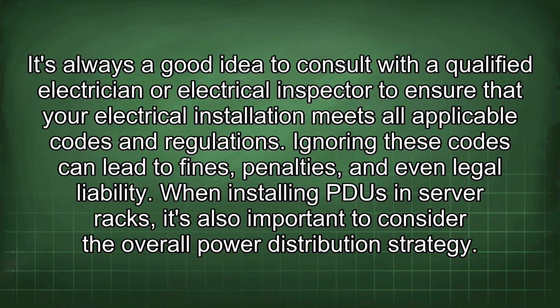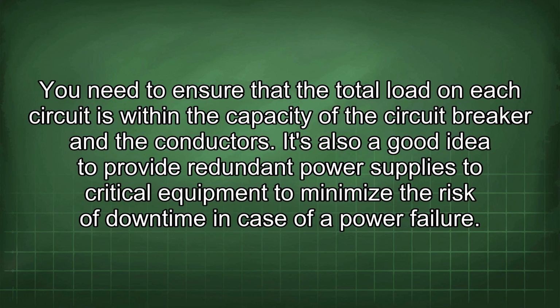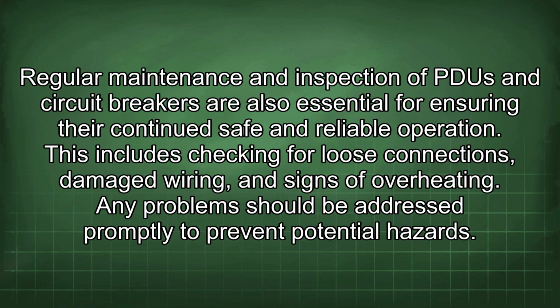When installing PDUs in server racks, it's also important to consider the overall power distribution strategy. You need to ensure that the total load on each circuit is within the capacity of the circuit breaker and the conductors. It's also a good idea to provide redundant power supplies to critical equipment to minimize the risk of downtime in case of a power failure. Regular maintenance and inspection of PDUs and circuit breakers are also essential for ensuring their continued safe and reliable operation. This includes checking for loose connections, damaged wiring, and signs of overheating. Any problems should be addressed promptly to prevent potential hazards.